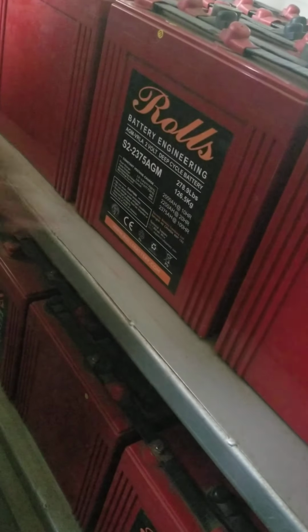2,375, but what you need to understand is we have 2,375 amp hour at C100. But this same battery, if you are discharging at C20, the capacity it will give you is 2,200 amp hour. If you are discharging it at C10, the capacity it will give you is 2,000. So your C rate determines, in actual fact, the capacity that the battery can deliver to you. Take a screenshot of that, I will explain it further in the class. Is that clear? Okay, let's move.